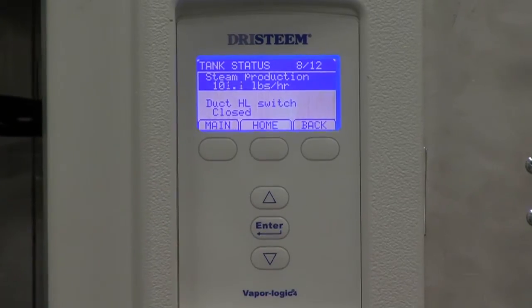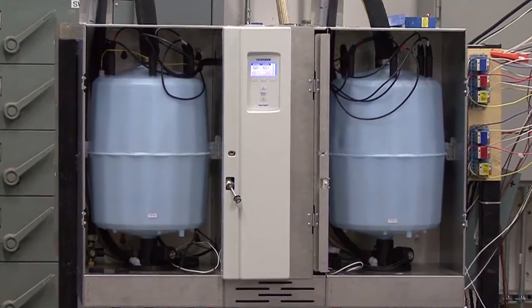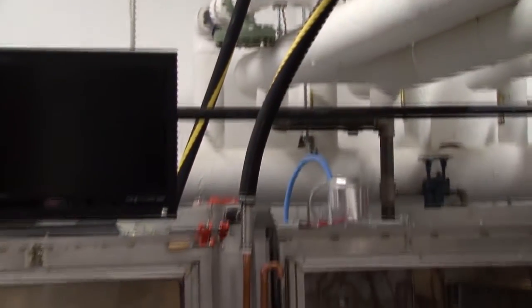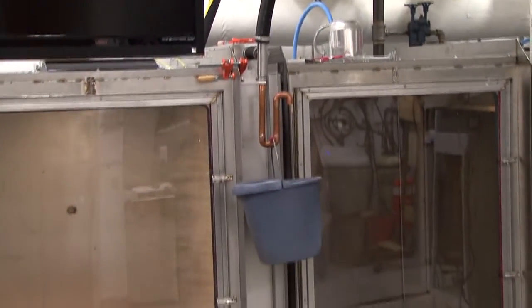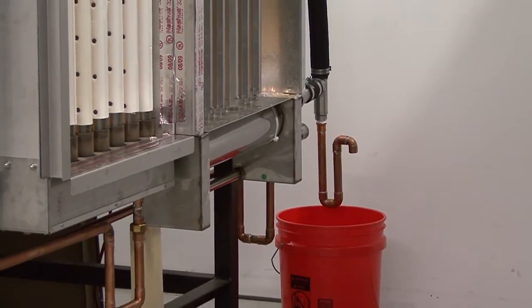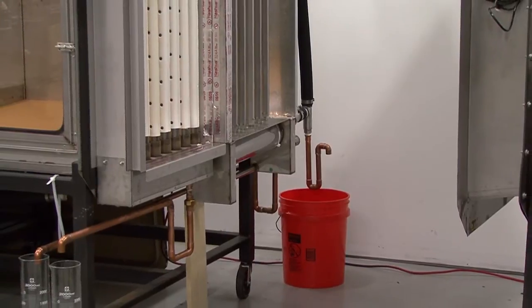Each dispersion assembly is receiving 50 pounds per hour of steam from a dual tank humidifier operating at 100 pounds per hour. Steam hose run lengths from the humidifier to each dispersion assembly are equal. Drip tees at each steam delivery header ensure that no steam hose generated condensate enters the dispersion assemblies.